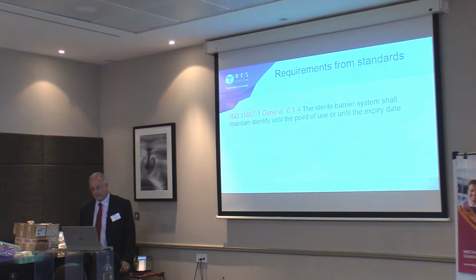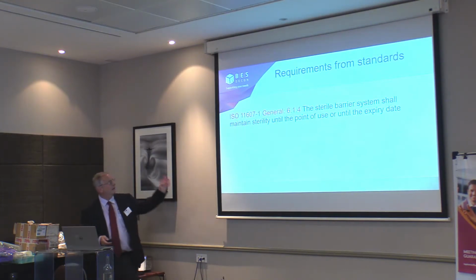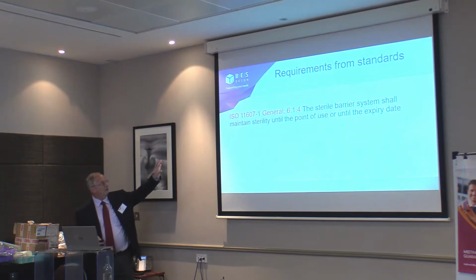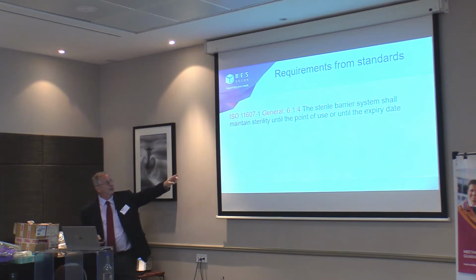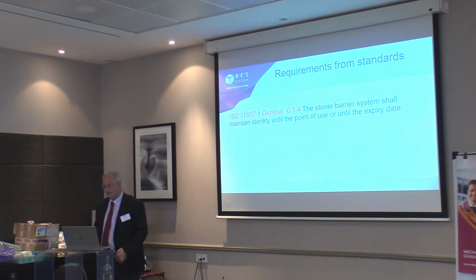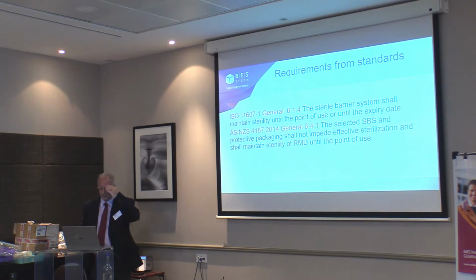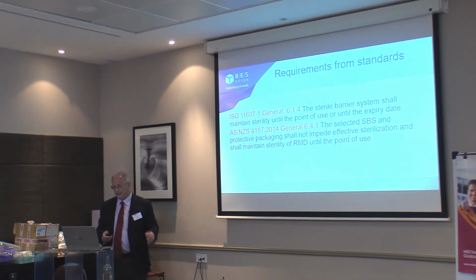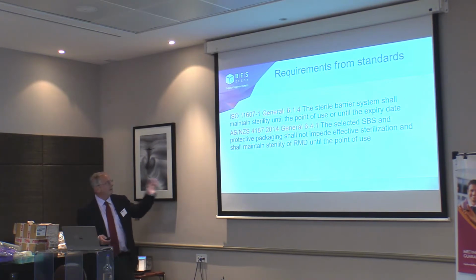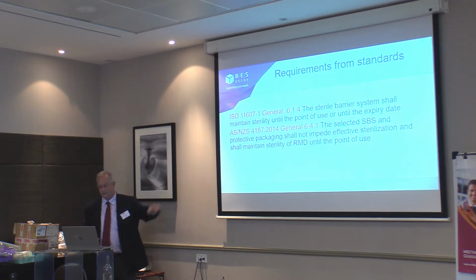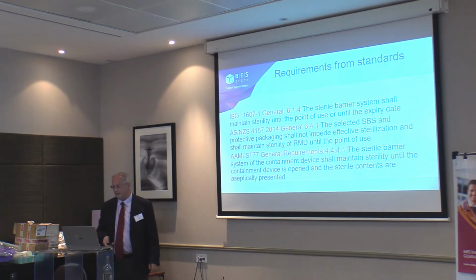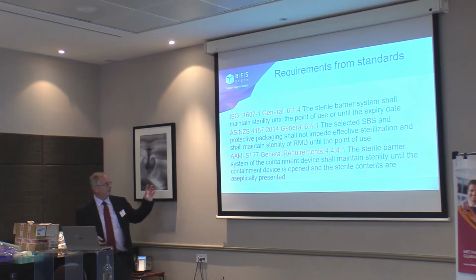Ingress. And just going back to a little bit of what the standards say, ISO 11607 Part 1 as it stands at the moment says that the sterile barrier system shall maintain sterility until the point of use or until the expiry date. And then there's an Australian version of one of the standards that says that the SBS shall protect the packaging and shall not impede the effective sterilization and maintain the sterility until the point of use. And the Americans have got their own AAMI standards, and there they say the sterile barrier system shall maintain sterility until the containment device is opened and the sterile contents are aseptically presented.